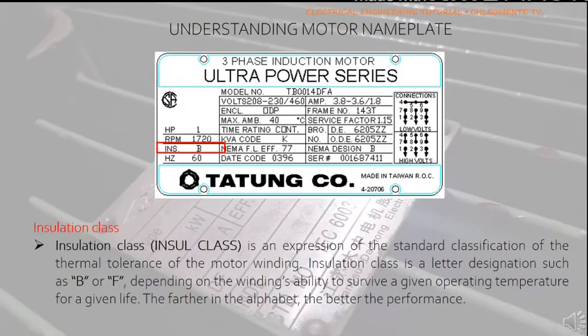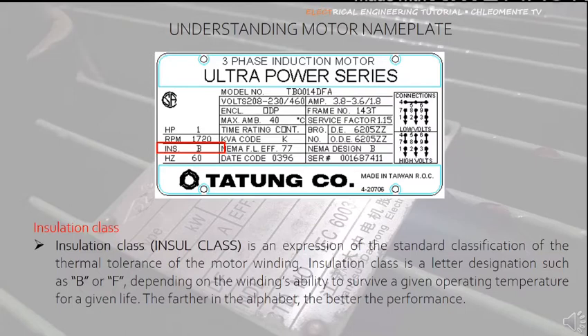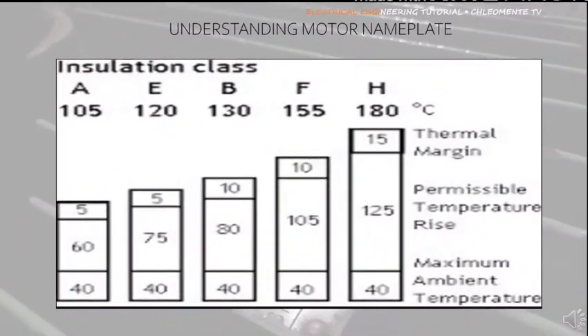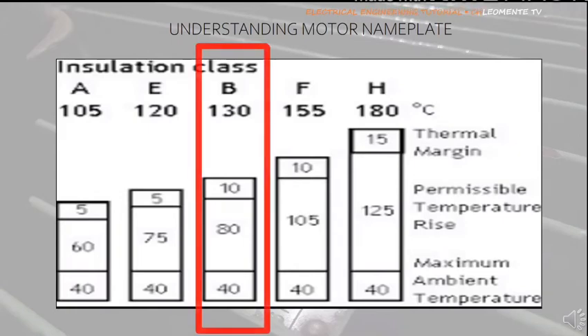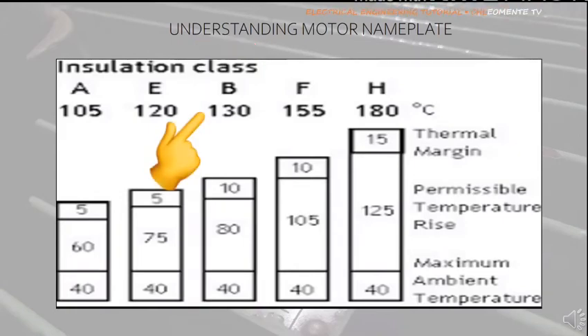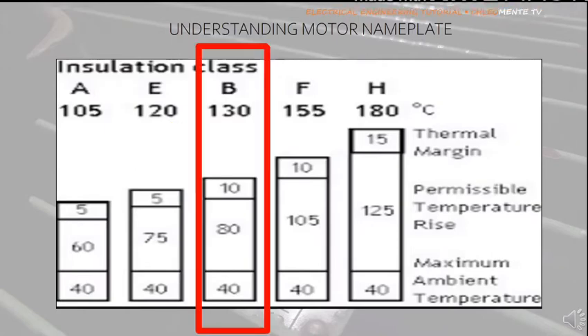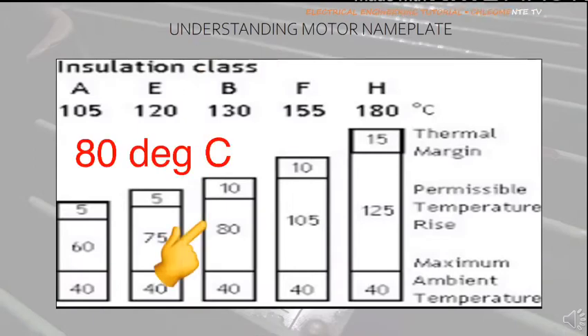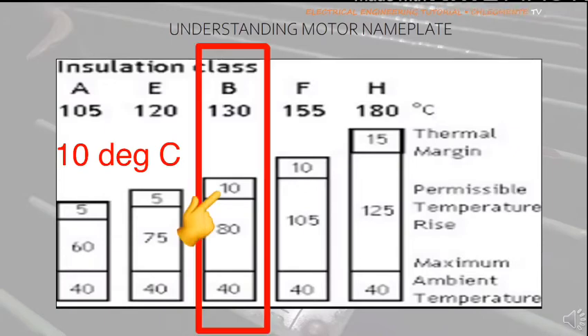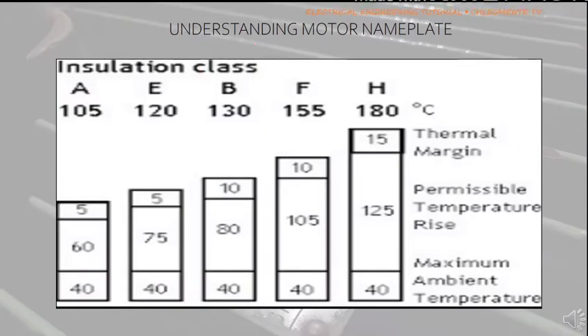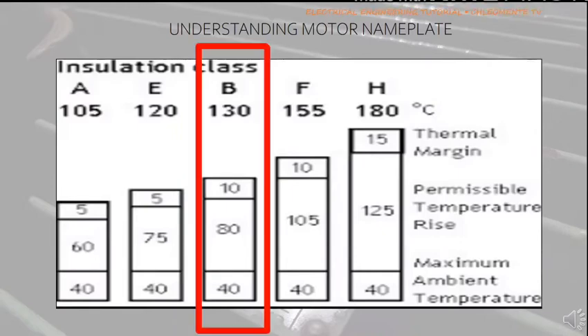Insulation Class, denoted by Insul Class, is an expression of the standard classification of the thermal tolerance of the motor winding. Each letter corresponds to the winding's ability to survive a given operating temperature. In this example, insulation class B means the winding of this 1 HP motor has a maximum of 130 degrees Celsius, with a maximum ambient temperature of 40°C, an 80°C permissible temperature rise, and a thermal margin of 10°C. Operating the motor 80°C above its maximum ambient temperature will degrade the winding insulation and in the long run cause motor winding failure.